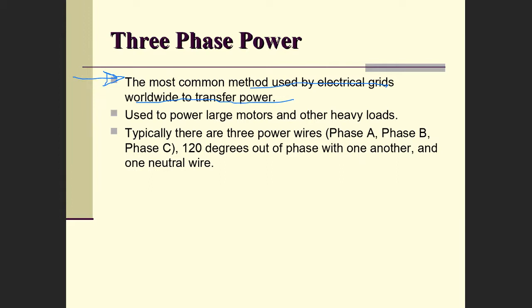Three-phase is typically used for high-power applications — large motors and any application requiring heavy loads. With three-phase power, we typically have a physical configuration that requires three power wires, one for each phase: phase A, B, and C. They are 120 degrees out of phase with one another. In addition to the three power wires, there is also a fourth wire, which is the neutral wire.